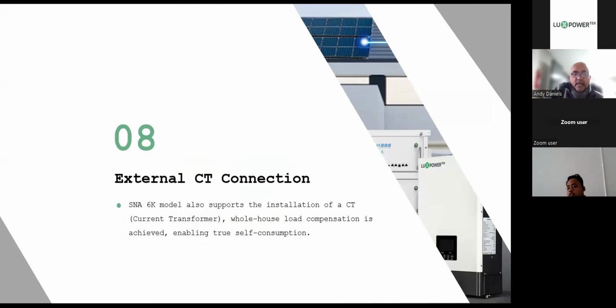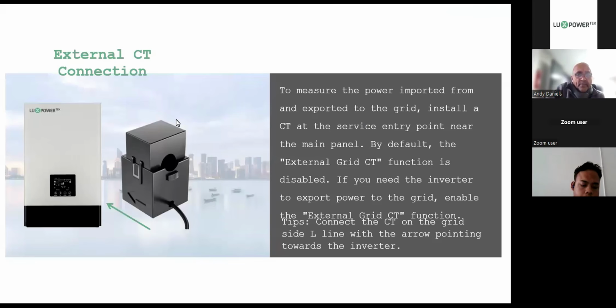Latest edition. Okay, external CT connection. Remember, the SNA 6 comes with a CT, the 5 does not. The 6 comes with an external CT, and it's optional to use it. You obviously have to use it if you're going to be grid connecting and you want to export. Then it is a requirement, especially here in Cape Town. This is a City of Cape Town requirement that you have an external CT connected, and you have to mark that on your application when you're doing the application. Like our LXP series, where the CTs are compulsory, with the SNA, it's not compulsory, because we do have an enable and disable function on the settings page where you can enable the external CT.